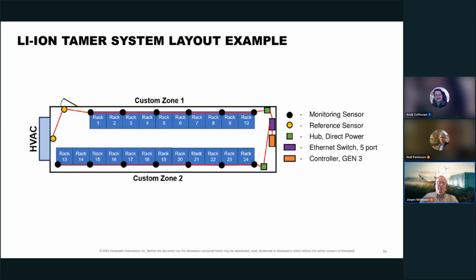So a typical installation for a battery storage system, like a container, is, as you see here, the black dots are the monitoring sensors on top of the battery rack. Depending on the rack design, it is either one sensor per two racks or one sensor per rack. There's a communication daisy chain, including a reference sensor. The reference sensor is used to avoid false positives from background gas coming through the door or from the HVAC system.